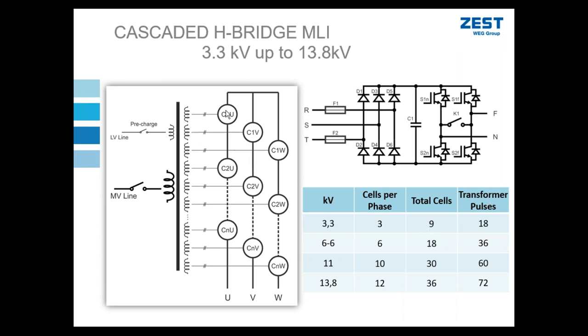And for each power cell that we put in series in a phase, we need to have its own separate isolated secondary supply, because each power cell is only able to switch a 690 volt maximum. And so I have to isolate these secondaries and give each one its own isolated supply. So if I have nine power cells to give me a 3.3 kV output, I need 9 secondary windings.